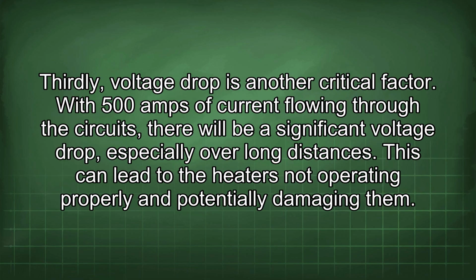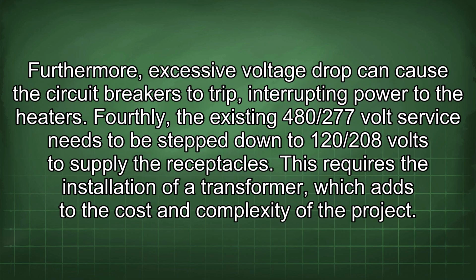Thirdly, voltage drop is another critical factor. With 500 amps of current flowing through the circuits, there will be a significant voltage drop, especially over long distances. This can lead to the heaters not operating properly and potentially damaging them. Furthermore, excessive voltage drop can cause the circuit breakers to trip, interrupting power to the heaters.